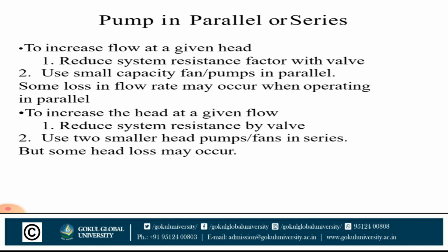Pumps in parallel or series. To increase the flow rate at a given head, reduce the system resistance factor with a valve, or use two small capacity fans in parallel. Some loss in flow rate may occur when operating in parallel. To increase the head at a given flow, reduce system resistance with a valve, or use two smaller head pumps or fans in series, but some head loss may occur.